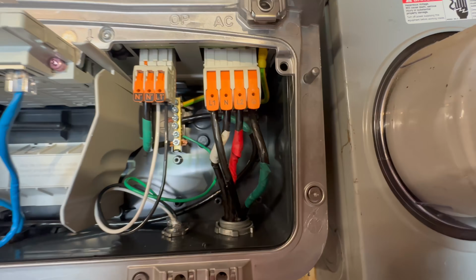Now, when you're connecting this up, there's some conflicting documentation in the instructions. They say only up to number 8 for these, but when you're connecting the ground, your ground from your outlet goes into your ground bar back here, and then you need to jump the neutral to the ground bar with a number 6 wire that has the ends permanently marked blue. Now, I don't have anything blue to mark these, so we're just gonna let this be as it is, but keep that in mind. And I did successfully get a number 6 in here—I'm not sure you're supposed to.